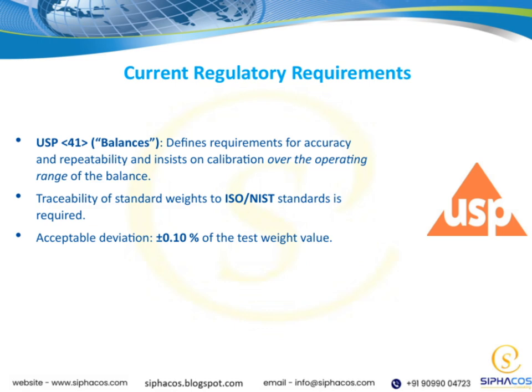Traceability is another key point here. All standard weights used for calibration must be traceable to recognized standards like ISO or NIST, which ensures consistency and international acceptance of your measurements. Finally, the acceptable deviation is set at plus or minus 0.1% of the test weight value. This means that your balance's measurements should stay within this margin to be considered compliant.